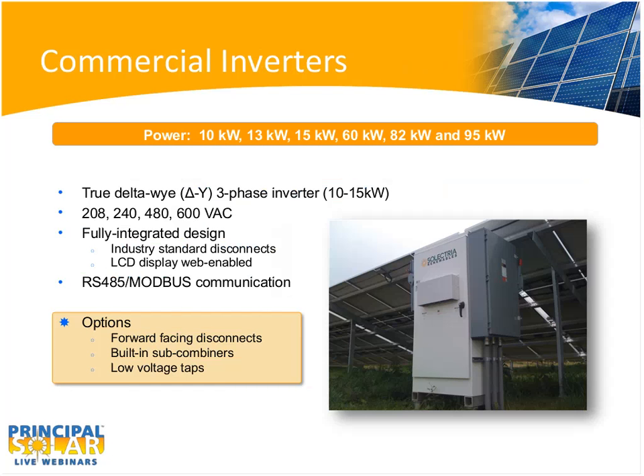As Kale mentioned, the 95 kilowatt inverter was chosen instead of larger central inverters for a number of reasons. One would be lower DC wire runs, but also added redundancy throughout the array. If you've got 18 or 19 inverters, that's a much higher level of redundancy. If there's ever an issue, you're only losing one small fraction of that array. That's compared to a 500 kilowatt inverter—if that were to go down, you'd be losing a lot more power production.